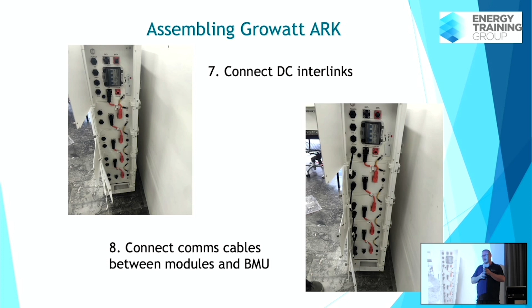This is probably an issue. I've seen this on inverters that need a termination plug - anywhere there's a Modbus communications loop, you need a termination plug at the end of the loop. I've gone to lots of sites to fault find with guys, and they've just left off that plug, and that's why their comms aren't working. I suspect it's going to be the exact same thing for this battery - guys will sit there pulling their hair out wondering why comms aren't working, and they'll have left that termination plug out. So that's something you want to get plugged in.